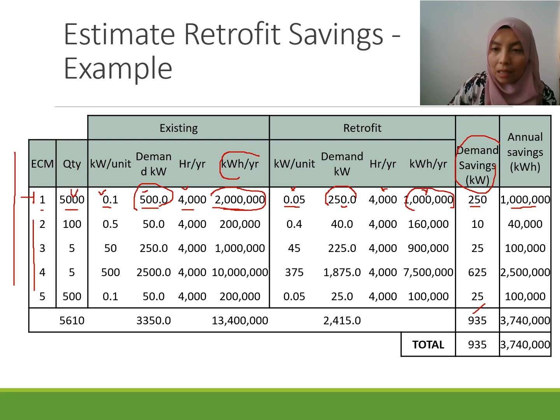Then you calculate the demand saving in kilowatt. The demand saving is 500 minus 250 kilowatt. For the annual saving, 2 million kilowatt hours existing minus 1 million kilowatt hours, so you get an annual saving of 1 million kilowatt hours. Then you do the same calculation for ECM 2, 3, 4 and 5. Then you calculate the total demand saving and the total annual saving in kilowatt hours.